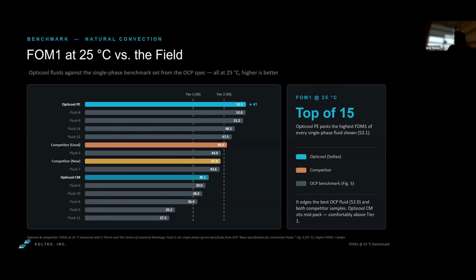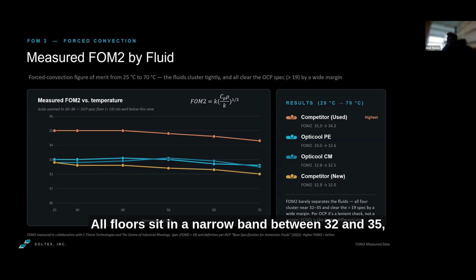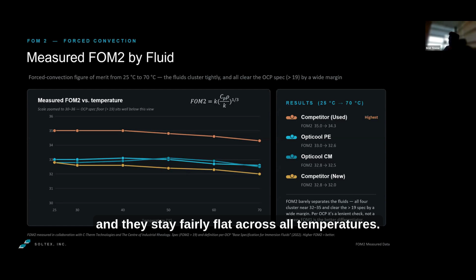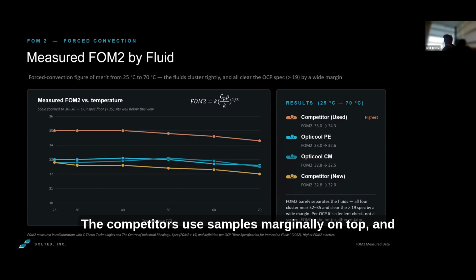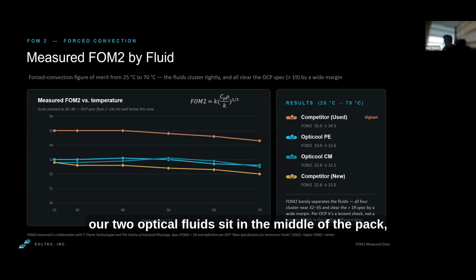This is the figure of merit that OCP expects to separate fluids the least, and our data shows exactly that. You'll notice the scale here is zoomed in, with very little change as the temperature changes. All fluids sit in a narrow band between 32 and 35, and they stay fairly flat across all temperatures. The competitor's samples are marginally on top, and our 2 Opticool fluids sit in the middle of the pack, essentially tied with the new competitor sample.